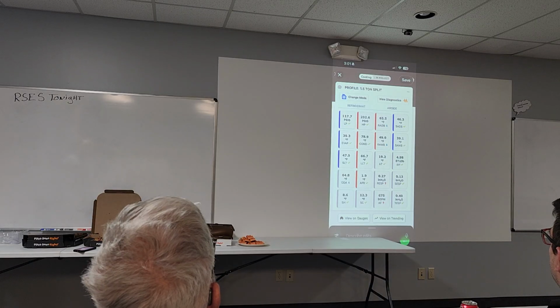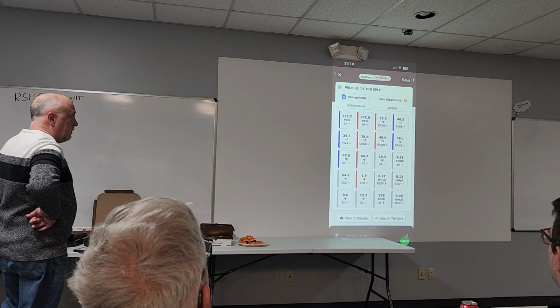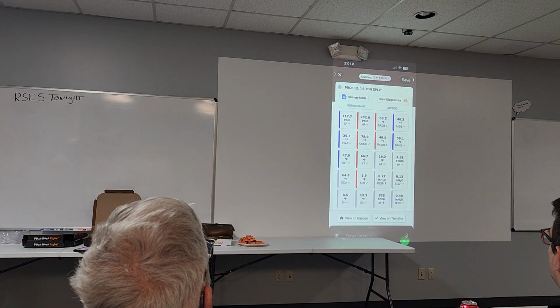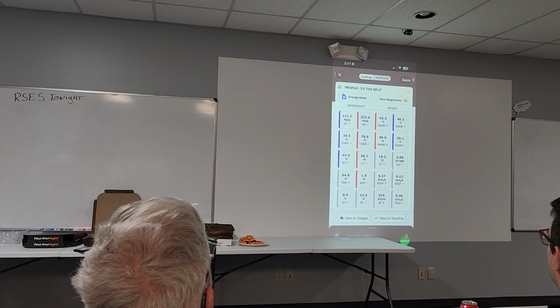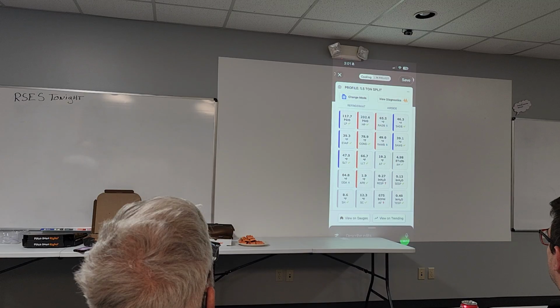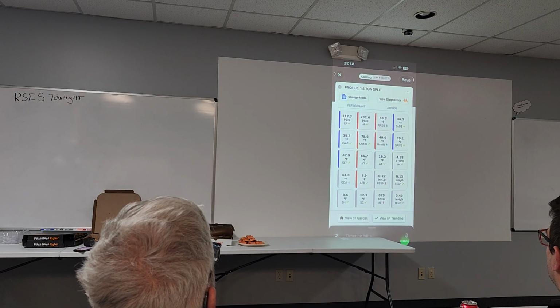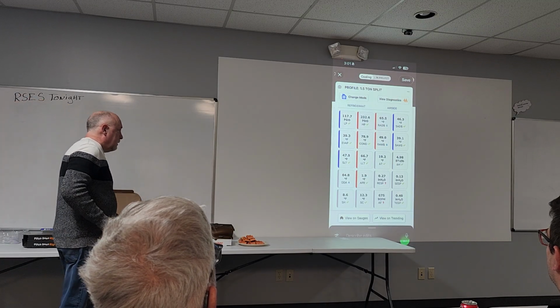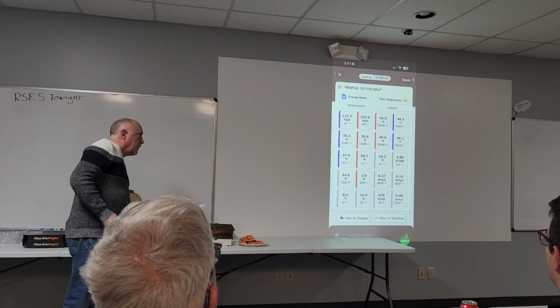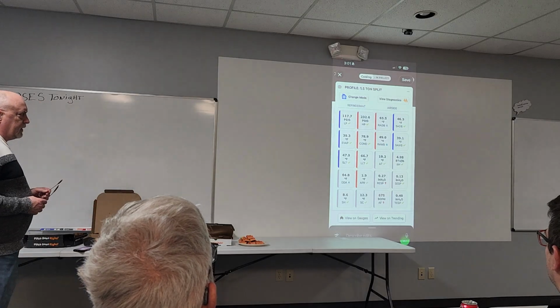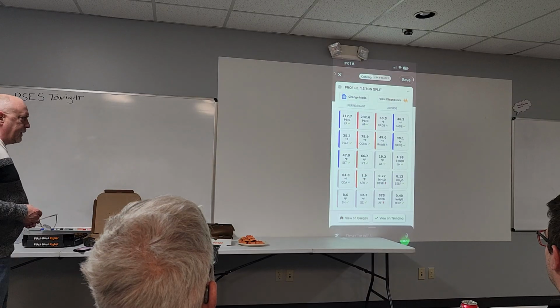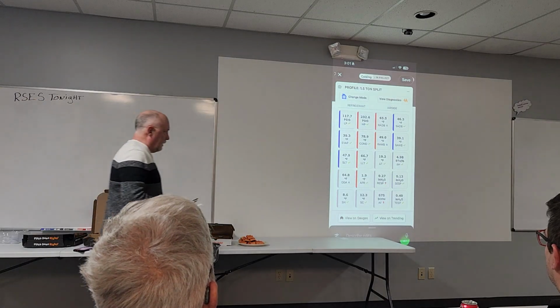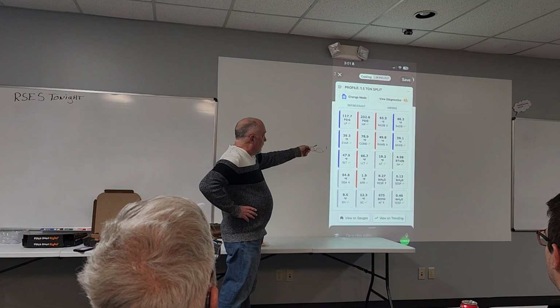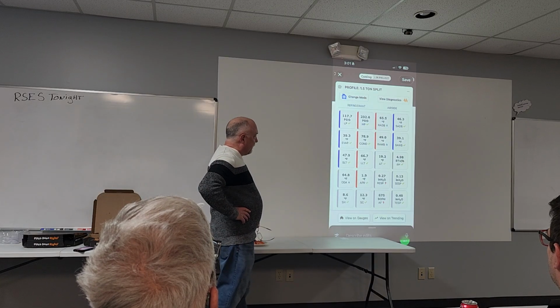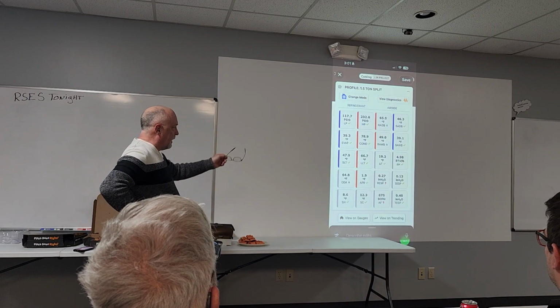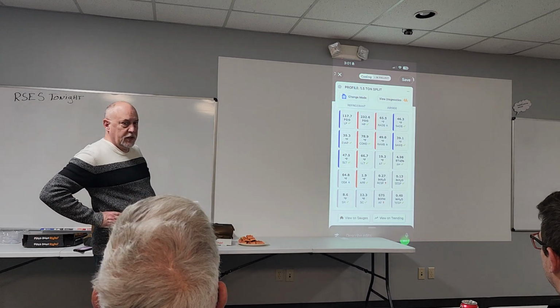anybody see anything in here? What's the refrigerant? R410A? Is there suction? And it knows that. If you don't know what any of the numbers are there, just let me know. It's a grid view, so it's just all the readings. The up and down arrows are telling you, like, well, liquid line temperature sure is low. Yep, and that's because look at my return air dry bulb at 65 degrees. So my liquid line temperature is low, but I do have 2 degrees of approach.